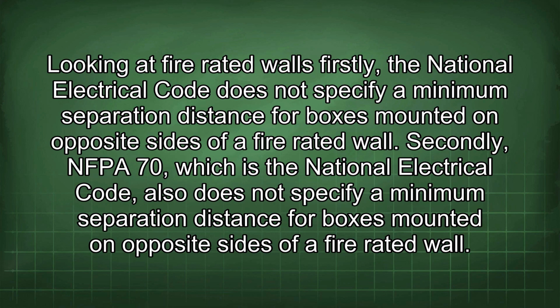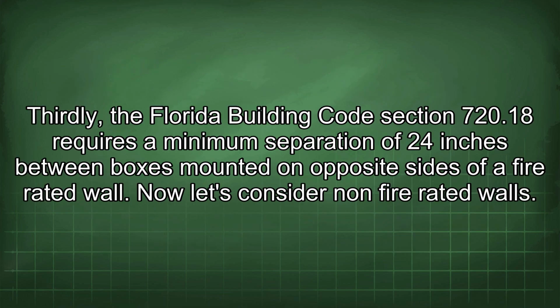Looking at fire-rated walls, firstly, the National Electrical Code does not specify a minimum separation distance for boxes mounted on opposite sides of a fire-rated wall. Secondly, NFPA 70, which is the National Electrical Code, also does not specify a minimum separation distance for boxes mounted on opposite sides of a fire-rated wall. Thirdly, the Florida Building Code Section 720.18 requires a minimum separation of 24 inches between boxes mounted on opposite sides of a fire-rated wall. Now let's consider non-fire-rated walls.